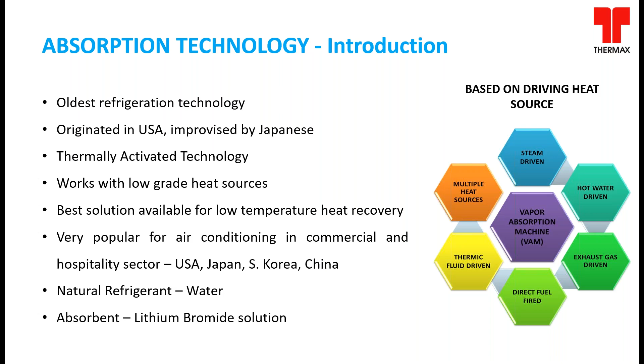Moving forward, as mentioned previously, there are various heat sources that can make this equipment run — maybe exhaust gases with temperatures over 250 degrees Celsius, hot water at 75 degrees and above, or steam starting from atmospheric pressure, which is waste heat in the form of vapor or flash steam. These can also drive an absorption chiller, or as mentioned, natural gas or oil can be used as heat sources.